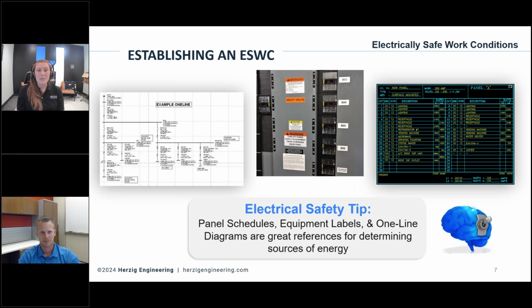Additional hazards, maybe it's a totally different result for your arc flash study now and you don't even know it. Could be different shock hazards. I've seen enclosures that said 208 volts and actually it had been refed and it was now like a 600 volt because it was an international piece of equipment that had been installed, but they didn't update the labels. It was just a whole mess. So yeah, you don't want to take anything for granted. Good point.